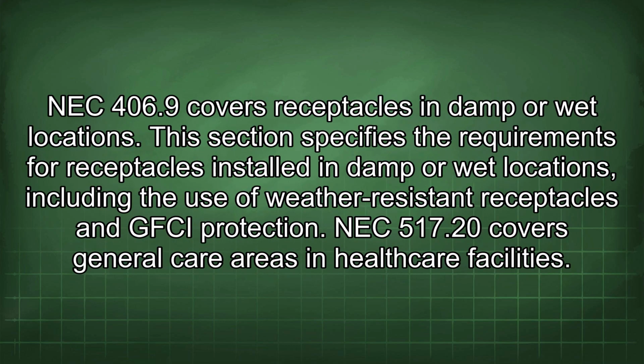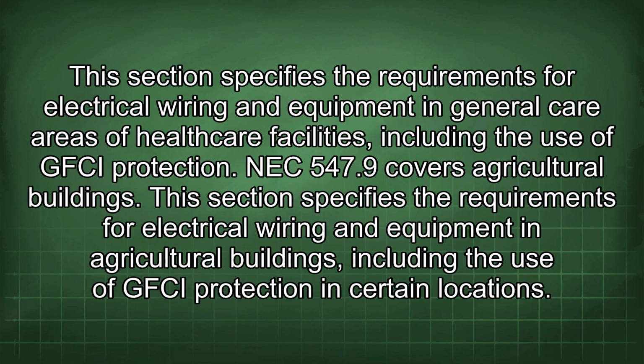NEC 406.9 covers receptacles in damp or wet locations. This section specifies the requirements for receptacles installed in damp or wet locations, including the use of weather-resistant receptacles and GFCI protection. NEC 517.20 covers general care areas in healthcare facilities. This section specifies the requirements for electrical wiring and equipment in general care areas of healthcare facilities, including the use of GFCI protection.